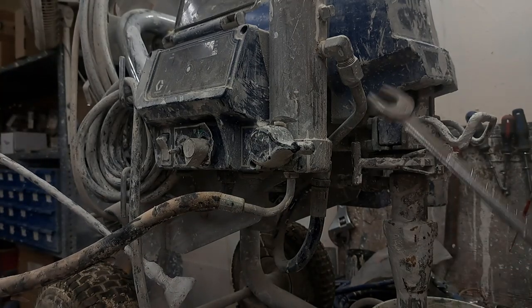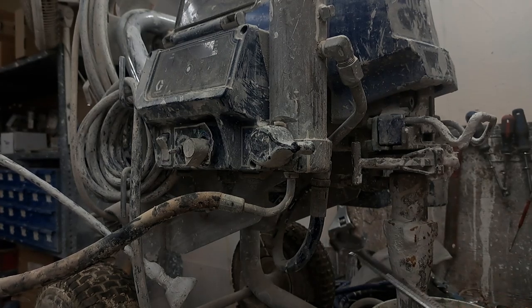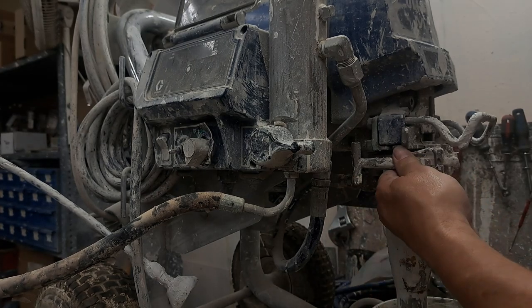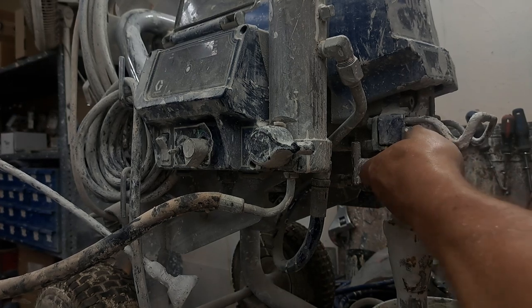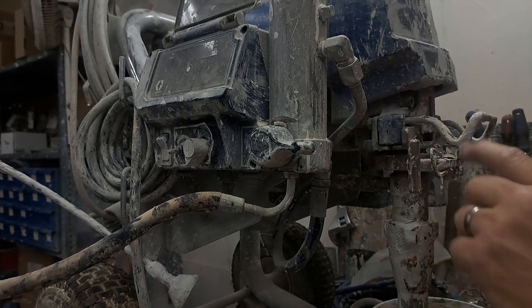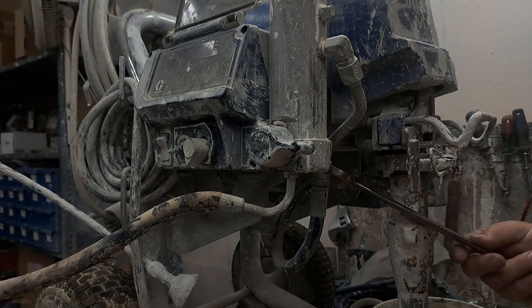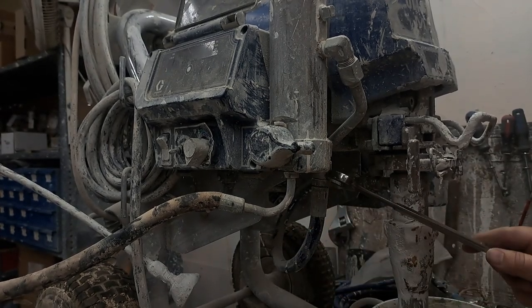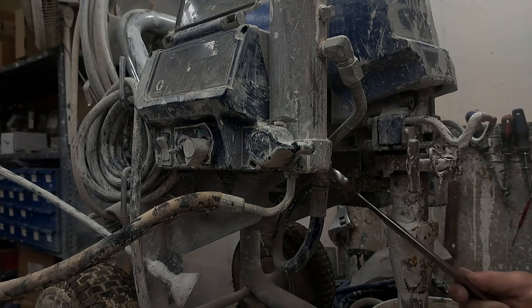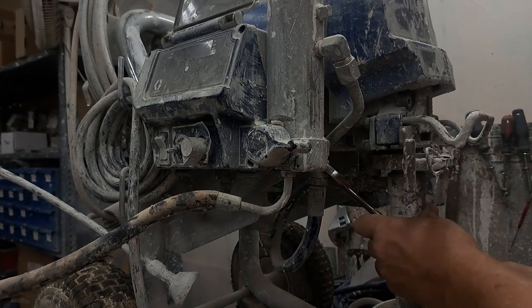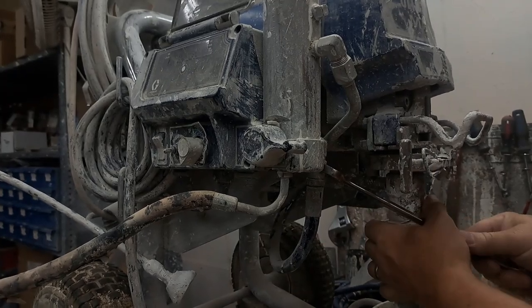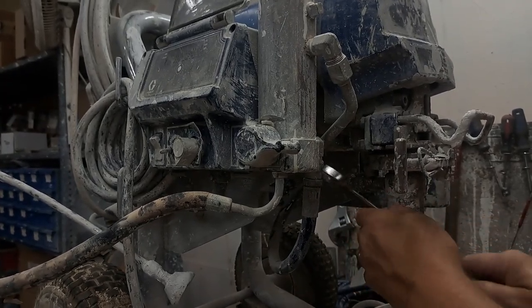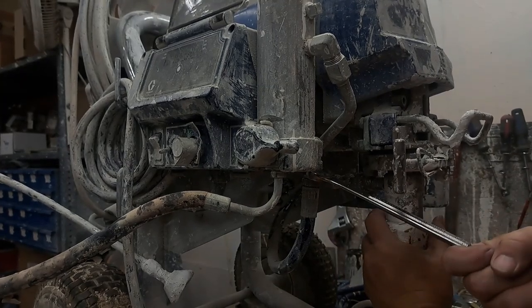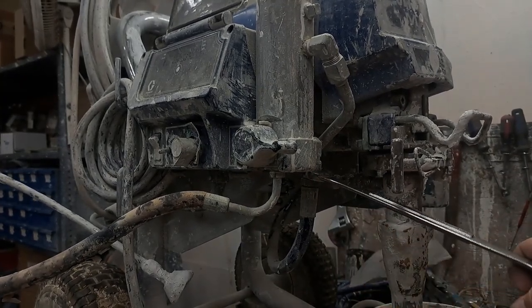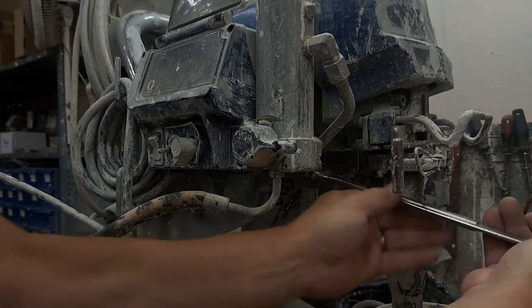Then right here you got your pump hose coming off the pump itself. This may be in the way, so what you can do on the ProContractor is flip it out of the way. On the standard series, that's not going to be an issue, but you're going to remove this hose that's sitting on the filter body here, and it's tight in there. So it can be a bit of an issue getting to. And the wrenches are kind of difficult because, like I say, it's a small area. So you don't have a lot of leeway with pull on the wrench.